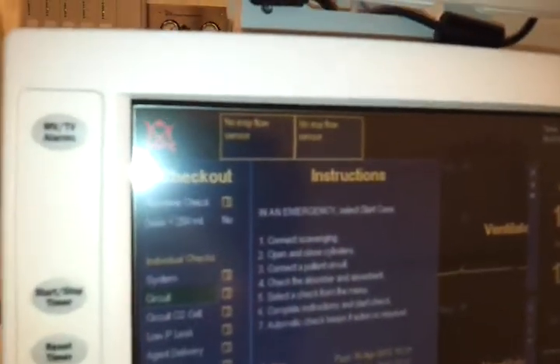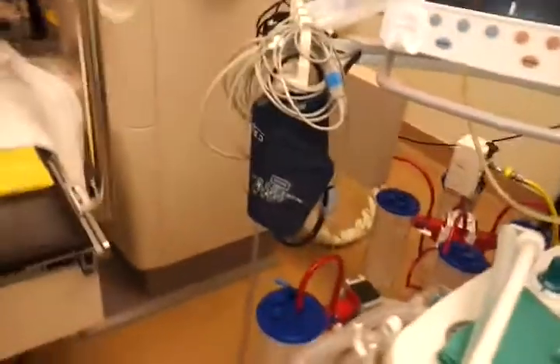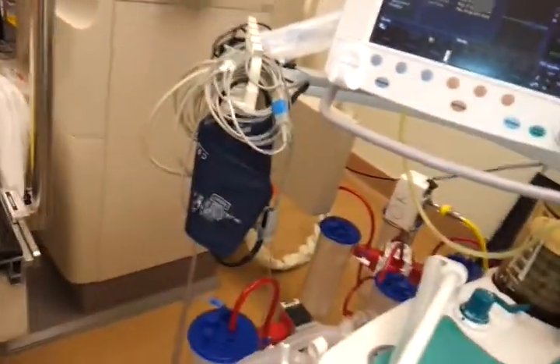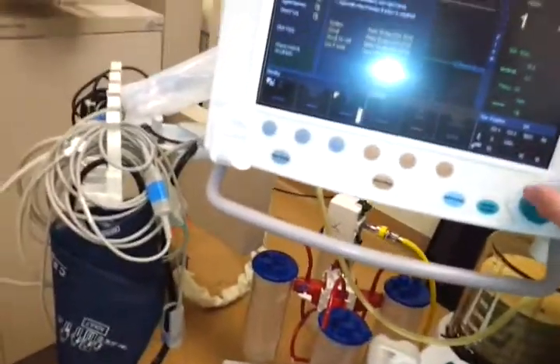So no inspiratory flow sensor, no expiratory flow sensor. So that's all you have to do, you basically plug it back in and it should go away, hopefully. There. Okay, so some people do it at the very beginning, some do it in the middle, just as long as it's done. Circuit test, so you go down to circuit, hit enter.